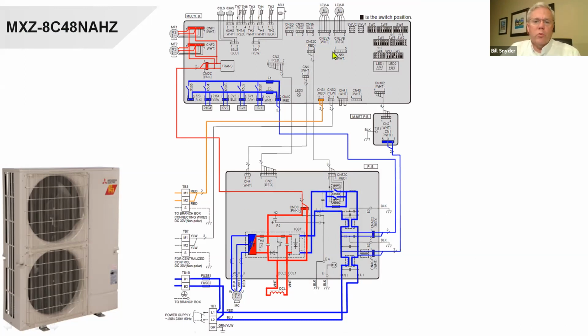But you'll see we only have 2 basic boards here. There's a little board here that powers the MNet, but there's 2 basic boards here. So you've got your noise filter and your power board all on one board. We come in here with line voltage, 208, 230, it cleans up the voltage somewhat and sends it over here to the IGBT. Again, that's insulated gate bipolar transistor, which changes that voltage over into DC, about 300 volts DC, and you'll see a little plus here and a little minus here. So we're going in here with AC, we're coming out with DC.